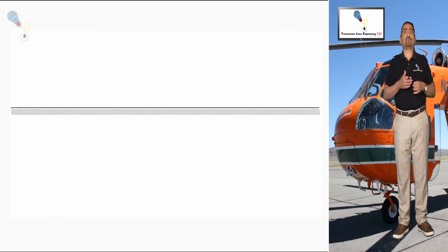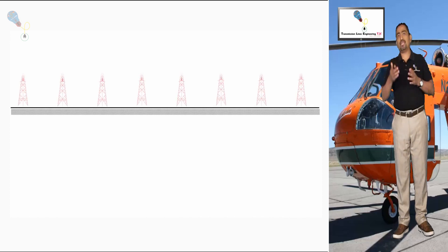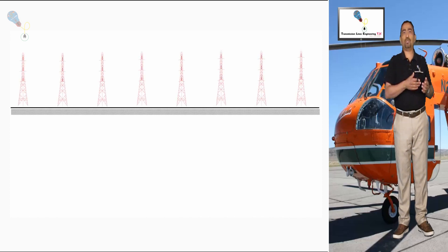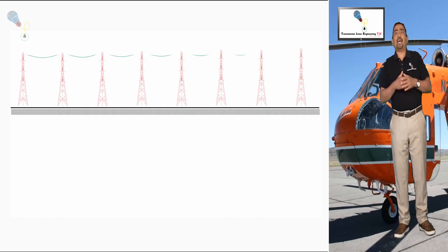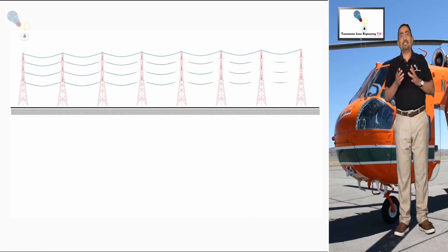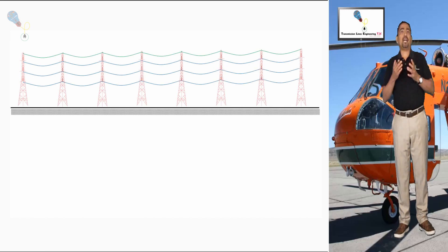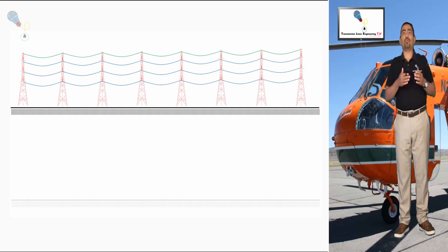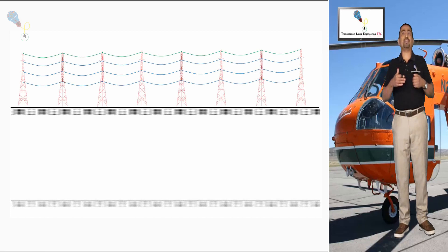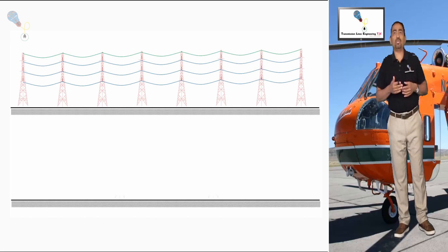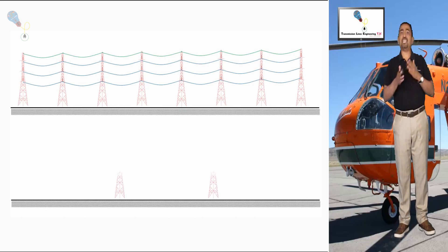In order to obtain the conductor sag, we must first have the ruling span. We will quickly define this term, which we will talk about in more detail later. At the beginning of a transmission line project, obviously there are no towers, no structures, no nothing. Therefore we don't have the spans between them, so we have to think of an average span or a representative one which will serve for the initial calculations.